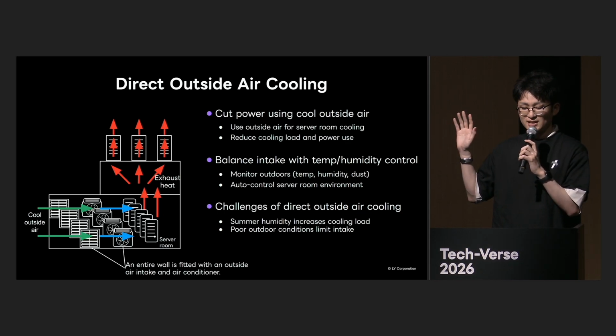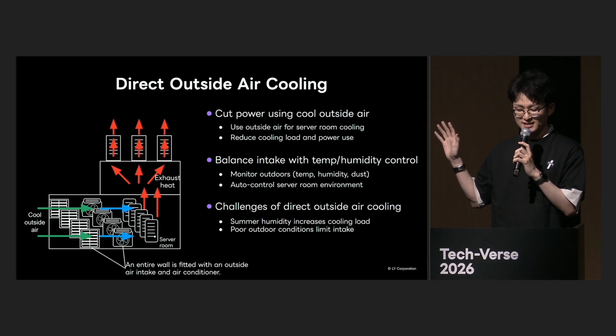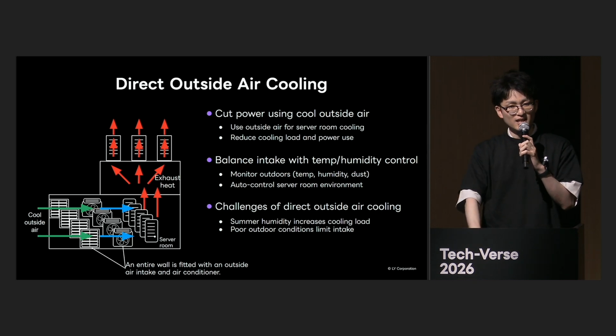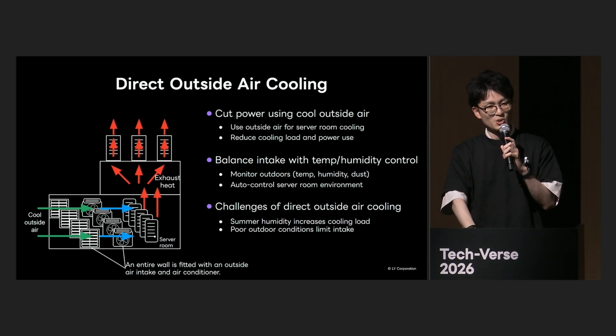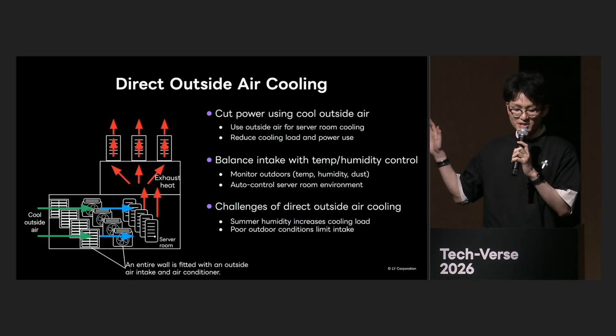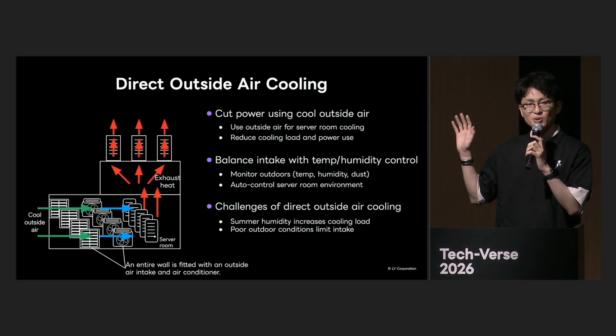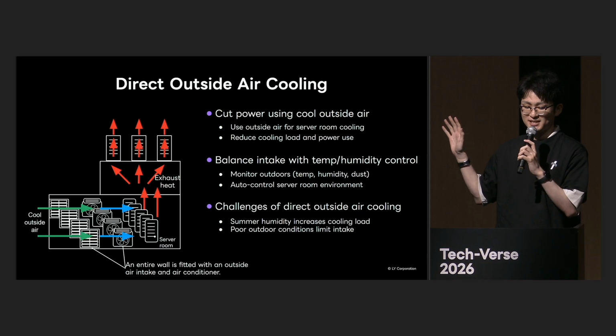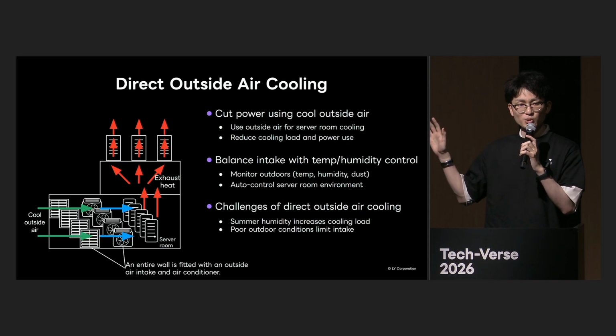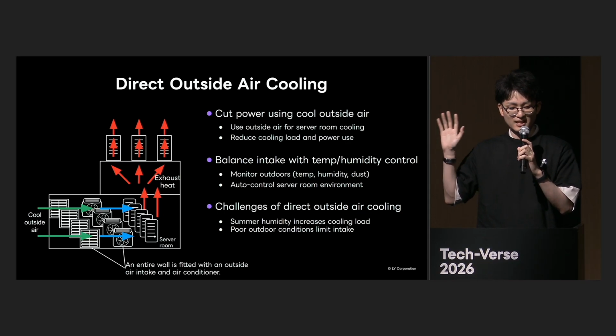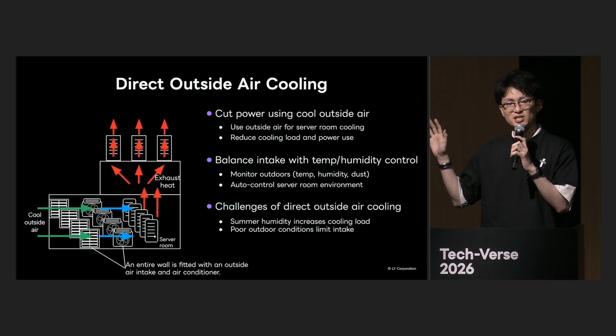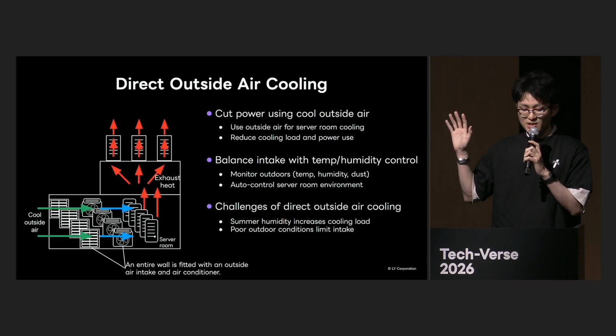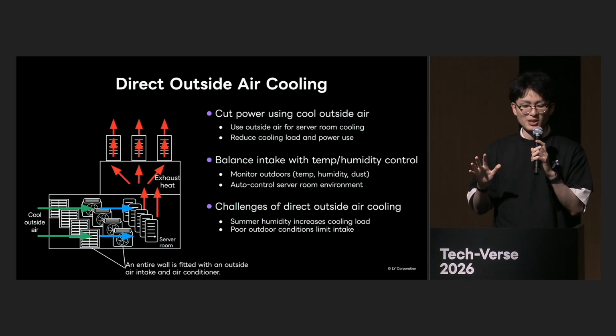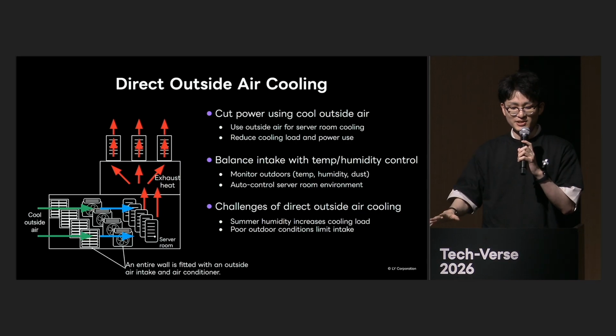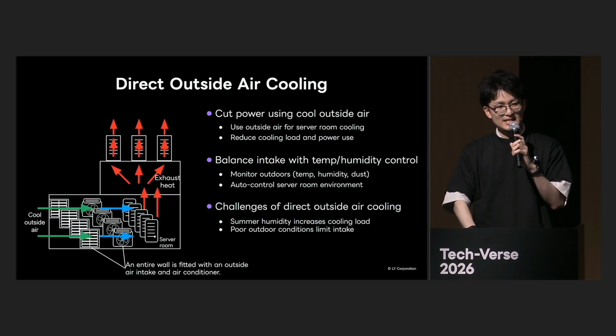First, this is a direct fresh air intake system that draws cool outside air directly into the server room. Normally, with equipment such as chillers that consume a large amount of electricity, we make chilled water and send it to cool servers. This system also directly incorporates cool outside air into the air conditioning system, reducing the power burden and power consumption.